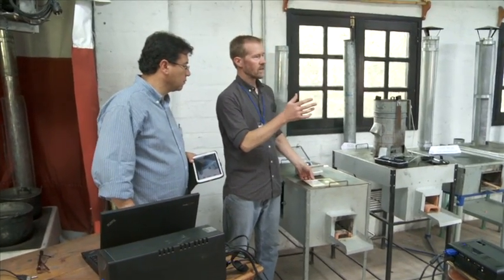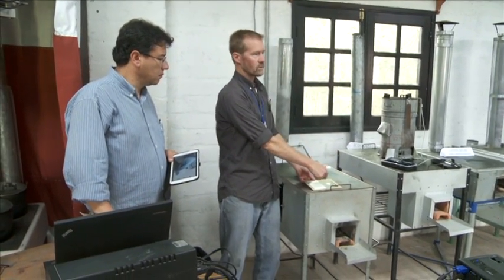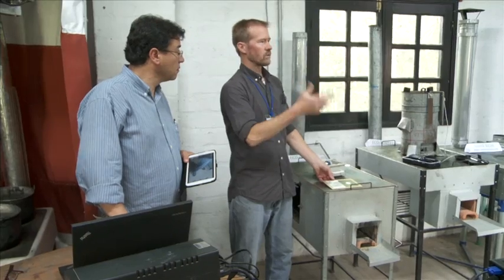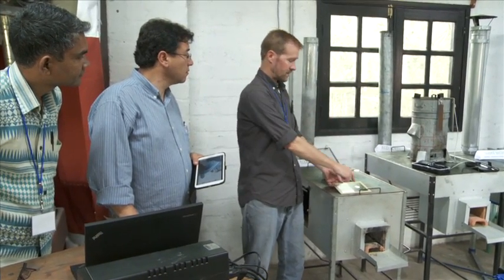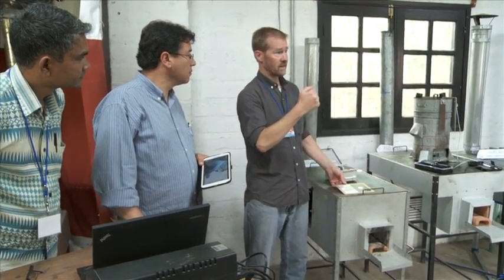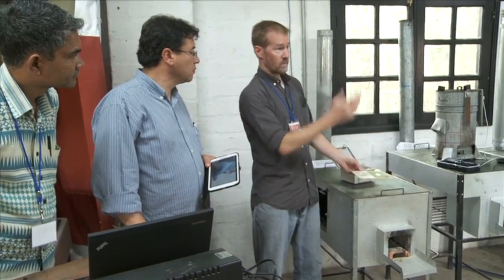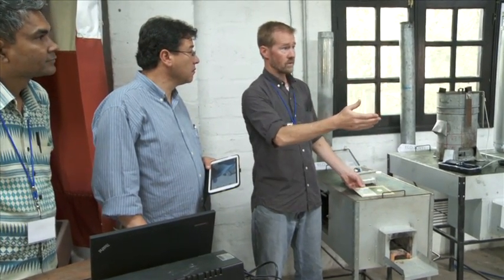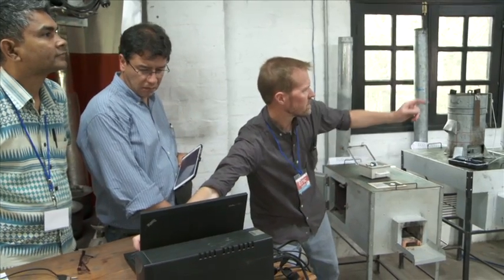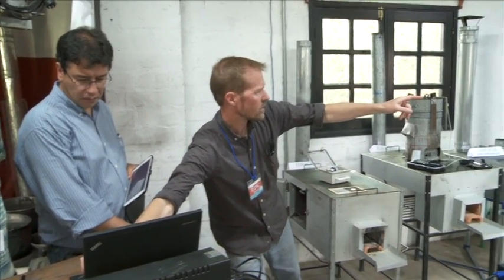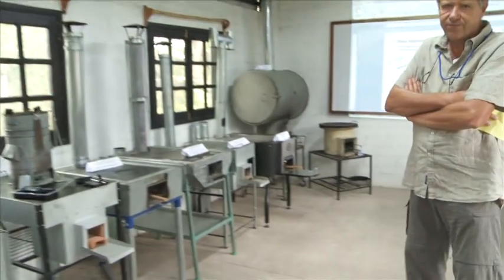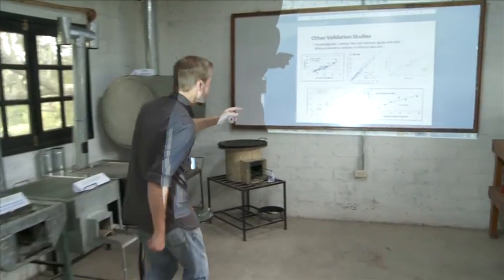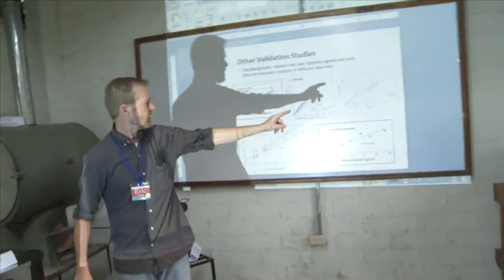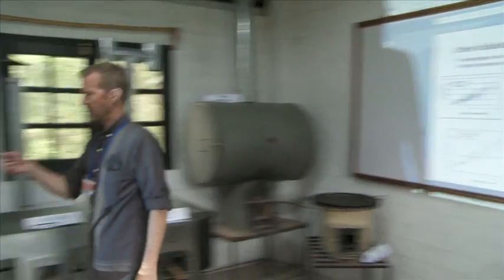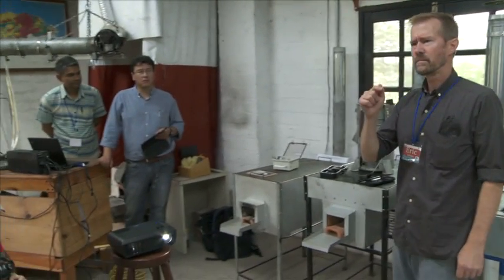No, so calibration is interesting. If you have some very different kind of particles you want to be measuring, if you pay for 20 or 30 analyses by thermal optical analysis, we can take those data and create a reference card specifically tailored for your application. We've done this for a couple of different places. This was our first calibration with Indian and California data, but we've been working with some other people, even using different instrumentation. This is a PASS unit, which is an instantaneous optical system.